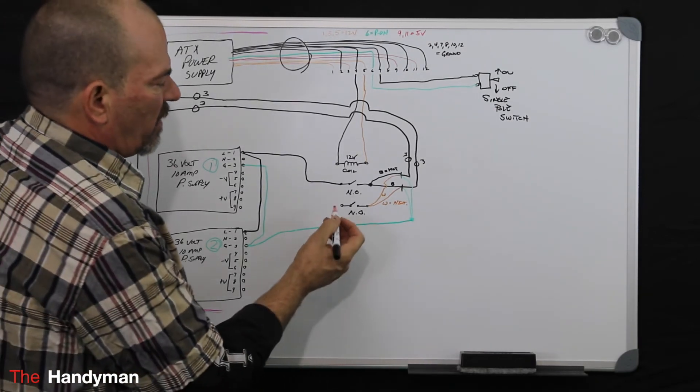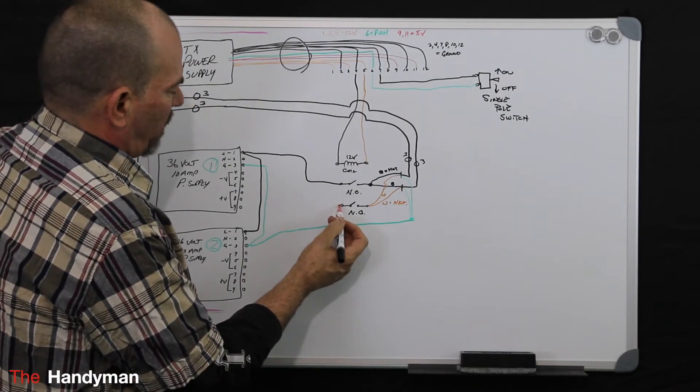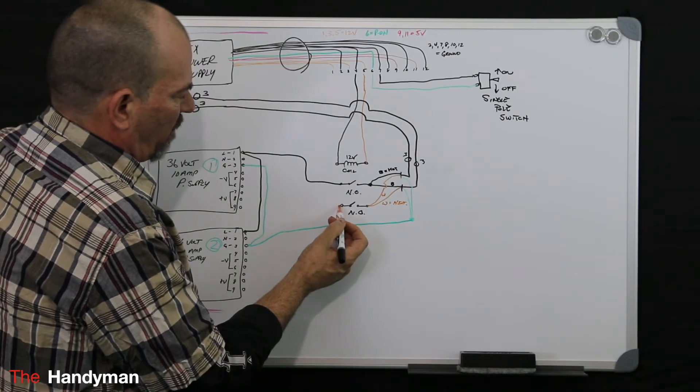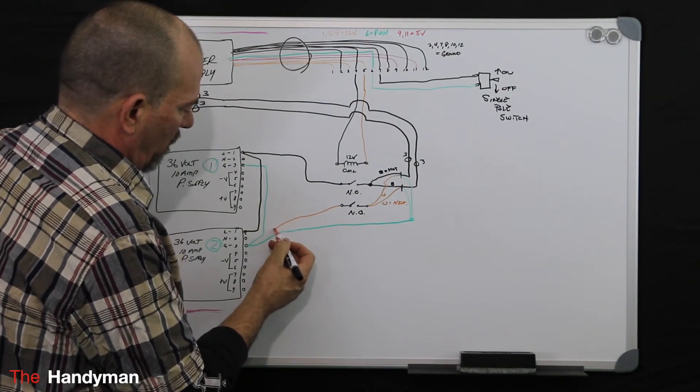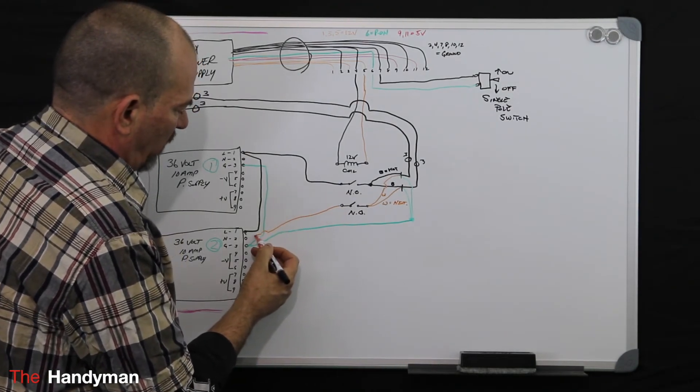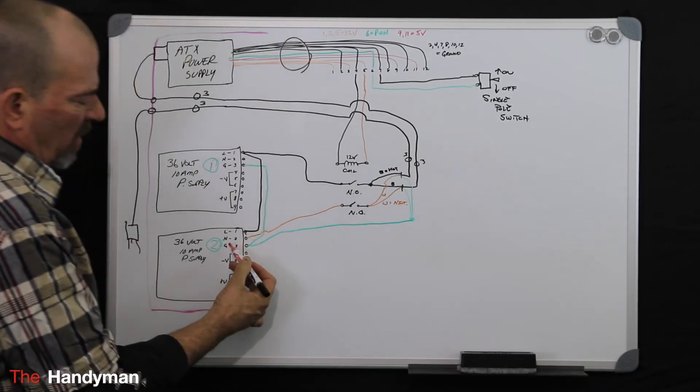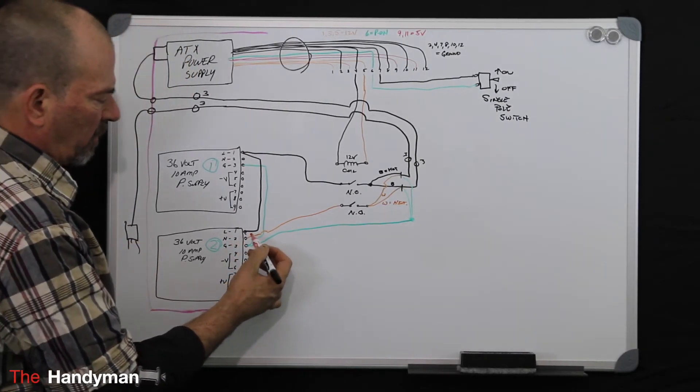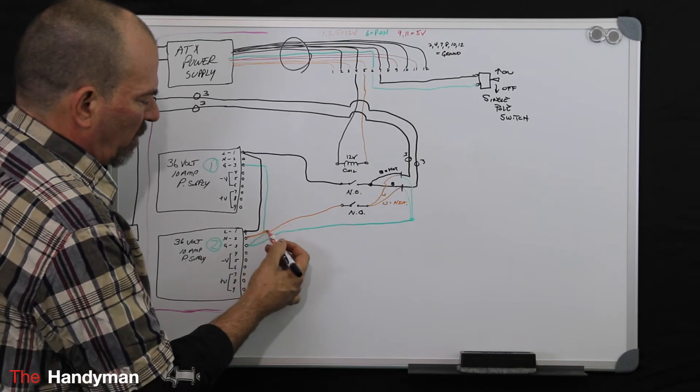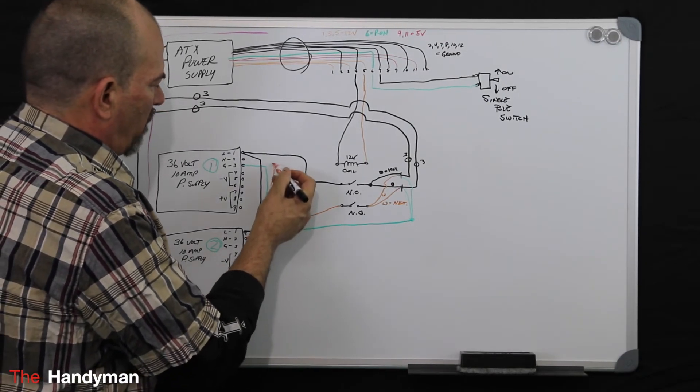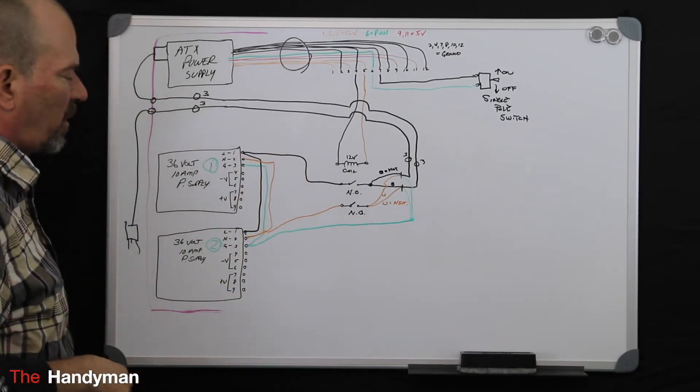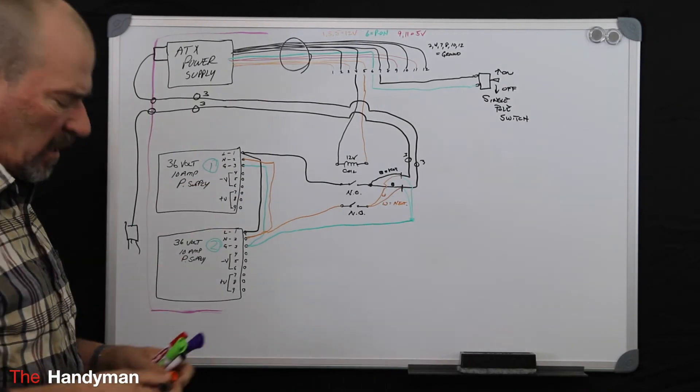And then on the other side of your other normally open contact, you're going to do the same thing. You're going to come down to terminal number two, which is for your neutral, make yourself a jumper, come up, and go to terminal number two. And it's as easy as that, it'll simplify things.